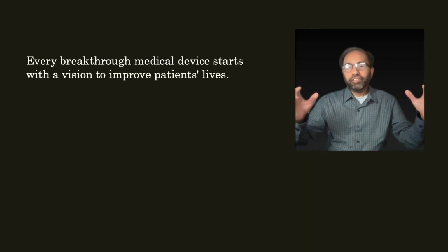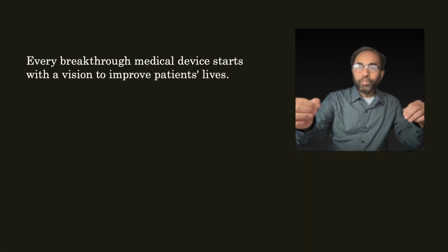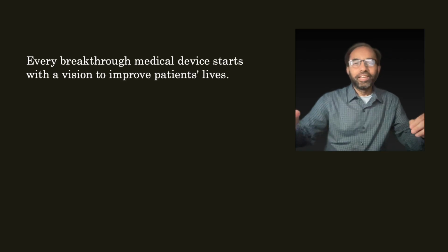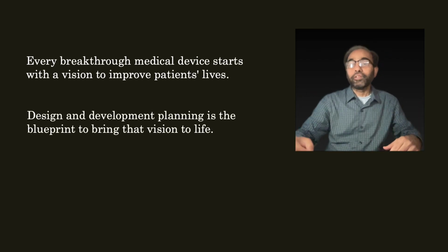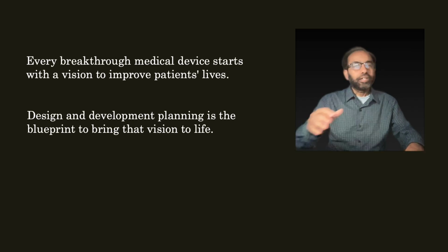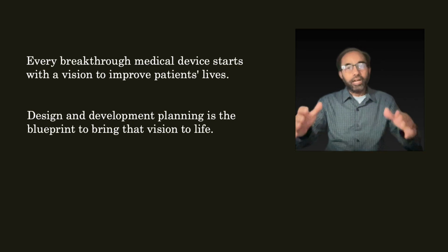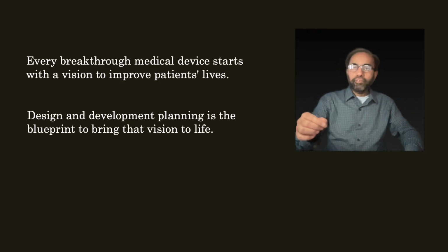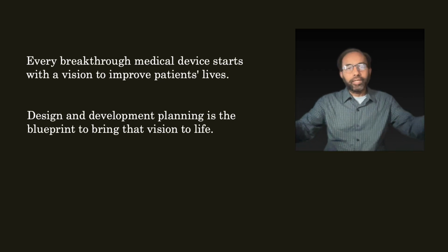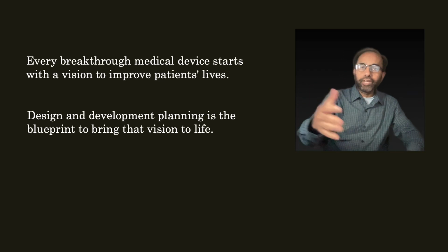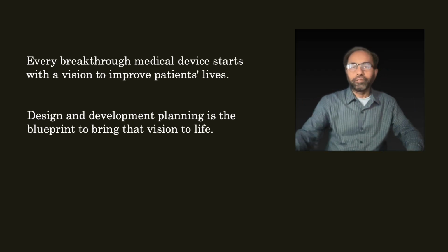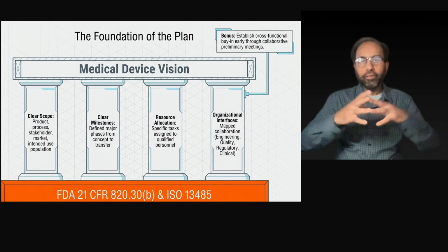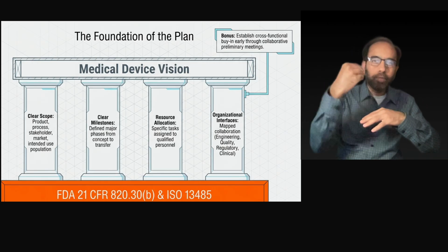Every breakthrough medical device starts with a vision to improve patients' lives. Design and development planning is the blueprint to bring that vision to life. Under FDA QMSR and ISO 13485, manufacturers must establish and maintain design and development plans that describe design activities and define responsibilities for implementation. In this section, we'll go over the foundation of that plan.